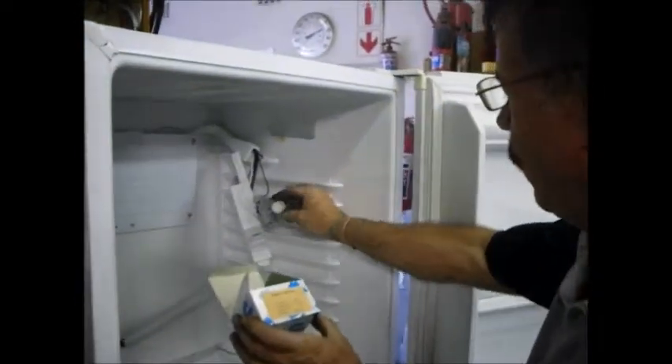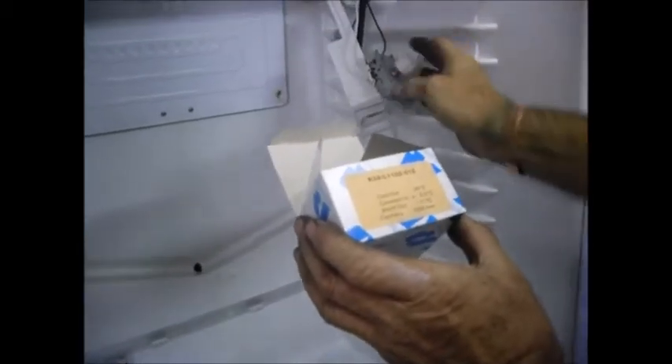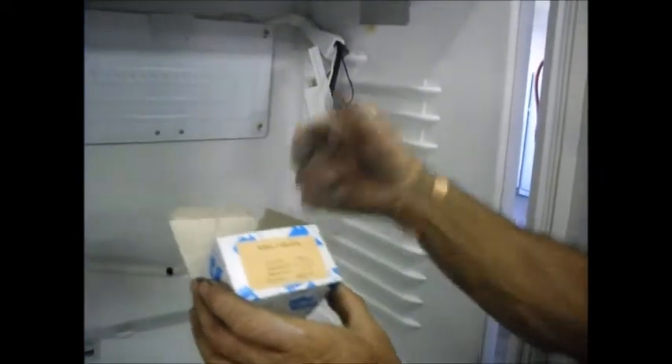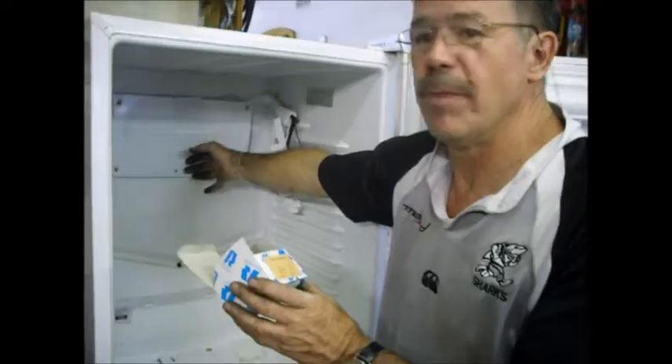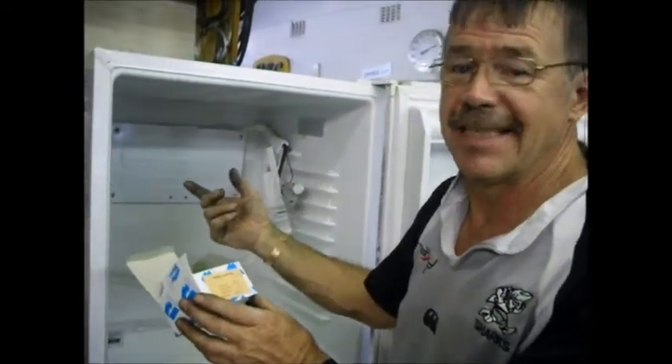I've got a Ranco thermostat box here and on the box it's got some specifications. It says cold out minus 26, constant in plus 3.5, warm out minus 11. Cold out means if you turn your thermostat to maximum temperature, it will break contacts on these two little screws where your sensor is mounted at minus 26. Warm out means if you turn it to its warmest position, it will switch the motor off on these two screws at minus 11. Constant in means once the motor is switched off, this plate will defrost — the ice will melt off this plate — and normally by plus 3.5 all the ice is melted and it restarts again. So we refer to this as cycle defrost.